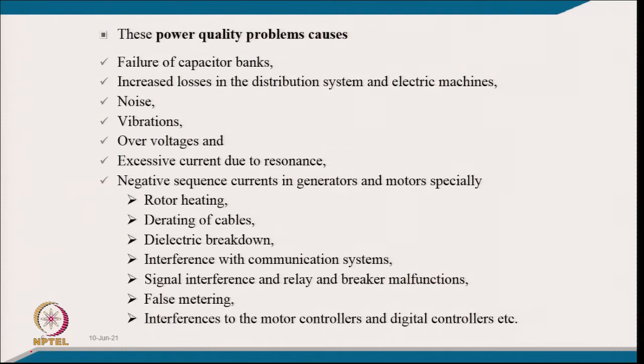Power quality problems cause failure of capacitor banks because if there are harmonics in the voltage, for higher order harmonics the capacitor has very low impedance and draws a very large harmonic current — amplifying the harmonic current. The capacitor banks get overloaded even with small voltage harmonics at the point of common coupling where the capacitor banks are connected.